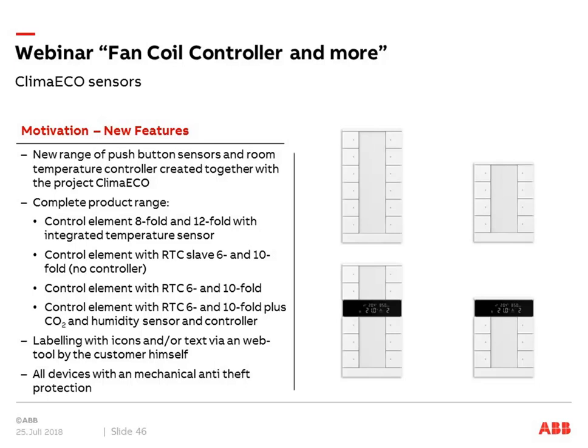Even more is available: the fourth level has the same components but with also integrated CO2 and relative humidity measurement and control functionality. These devices allow controlling room temperature, air quality/CO2, and humidity in the room. For the right actuators: the fan coil controller is mainly for temperature control, but with the fan or a 0-to-10 volt output for a damper you can get more fresh air into the room to improve CO2 levels. Further actuators can adjust humidity. It's real room climate control possible with these components.